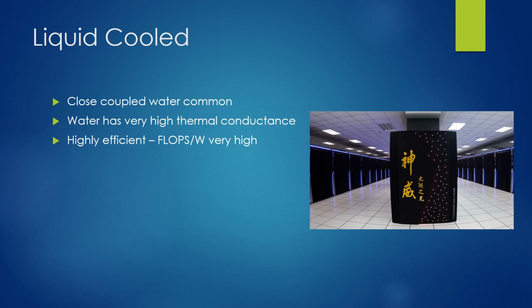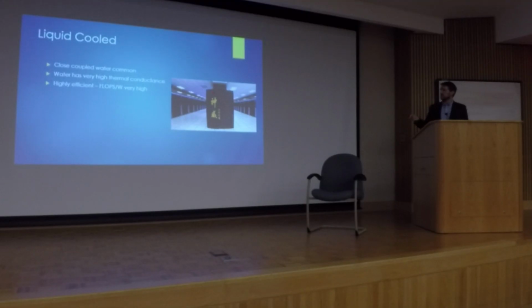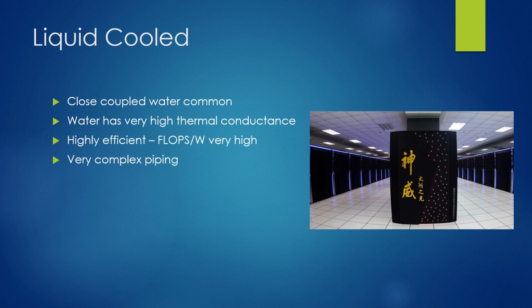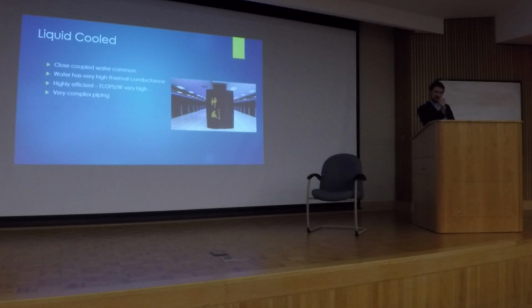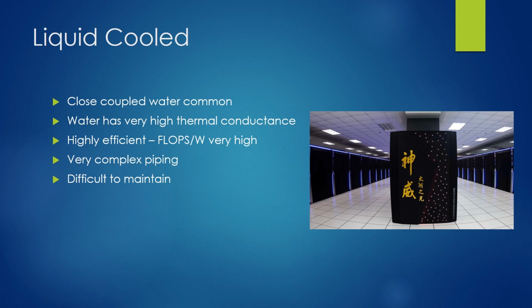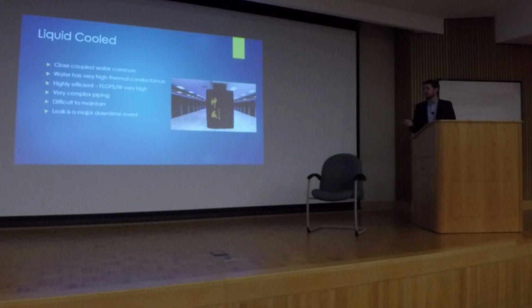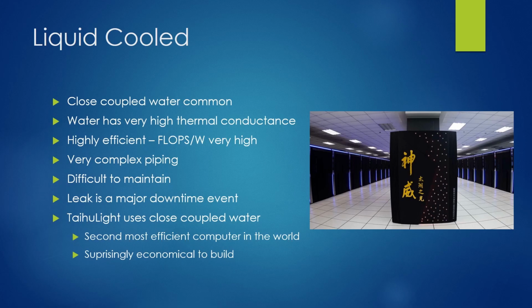So going back to this TaihuLight HPC computer, which is again the fastest in the world. It's in China. It has that close coupled water cooling to the chip, which means that there's very complex piping within all these racks where there's one little pipe that goes to each compute core and then goes back out. It can be pretty difficult to maintain, and if there is a leak, it can be a major downtime event. So there are pluses and minuses, but it makes it the second most efficient computer in the world. So you talk about the flops, those floating point operations per second, per watt. That can be incredibly high with this type of a setup.